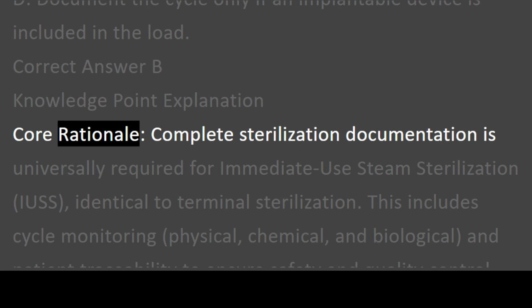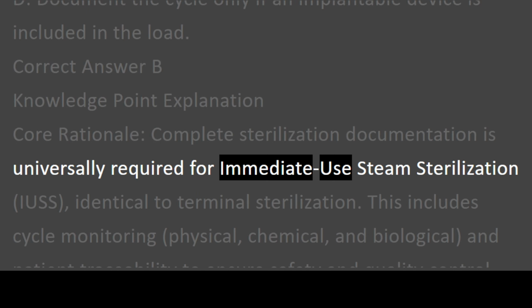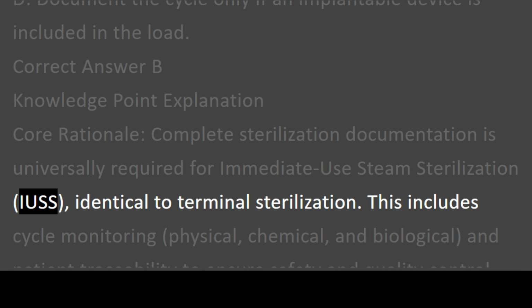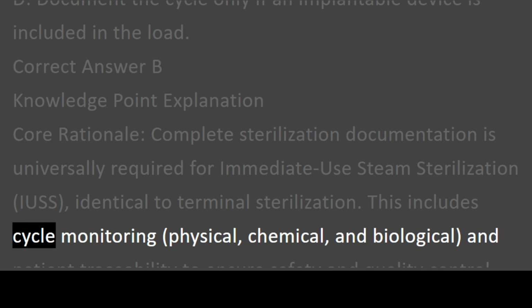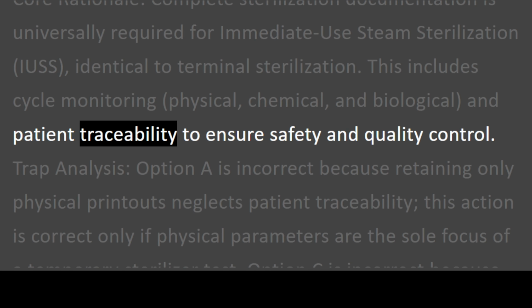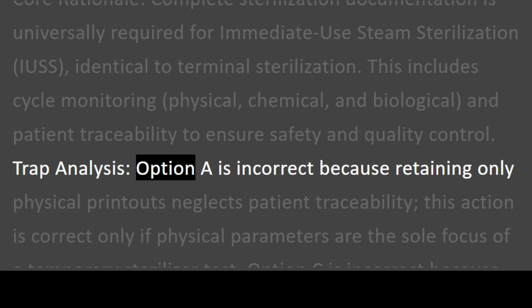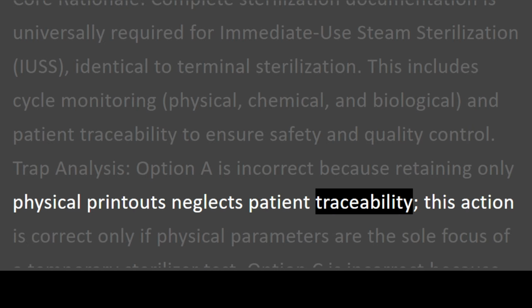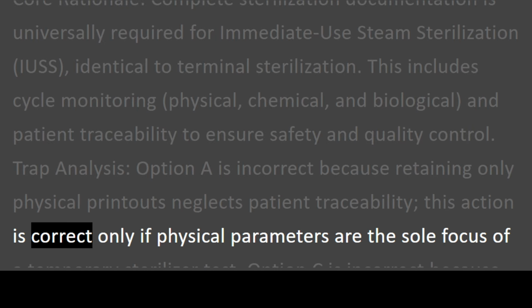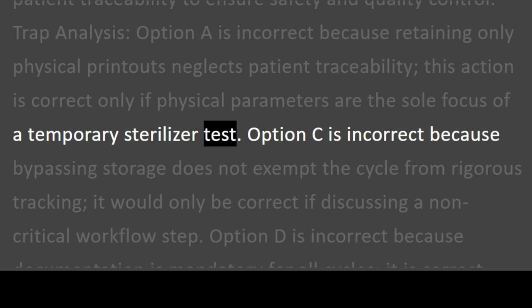Core rationale. Complete sterilization documentation is universally required for immediate use steam sterilization, IUSS, identical to terminal sterilization. This includes cycle monitoring, physical, chemical, and biological, and patient traceability to ensure safety and quality control. Trap analysis. Option A is incorrect because retaining only physical printouts neglects patient traceability. This action is correct only if physical parameters are the sole focus of a temporary sterilizer test.